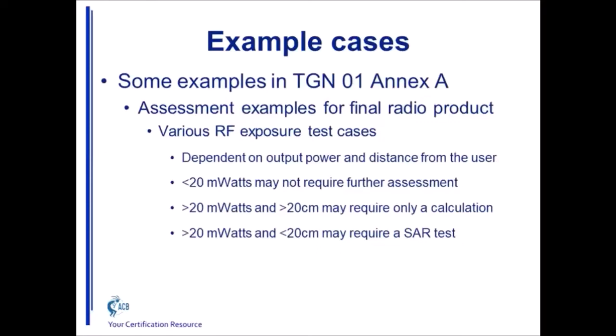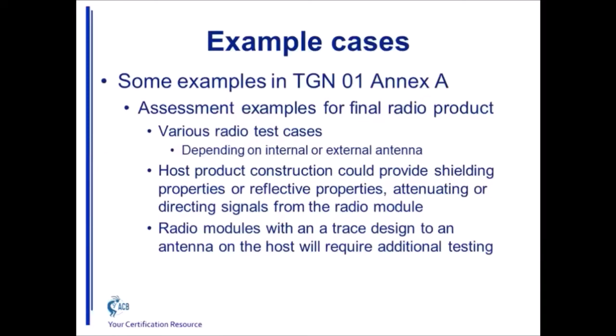However, if you're at a higher power and you're close to the body, this could be the head or your hands or your body itself, you may require a SAR test. So one of the assessment issues for a final radio product, again, depends on the various radio test cases. And this can be viewed as whether it has an internal or external antenna, because the host product construction could provide shielding of the module if there's an internal antenna, or it could affect spurious emissions and field strengths from spurious emissions, because you may have some shielding that could reflect and focus energy at some frequency. That's possible. And in the end, if you've got a radio module with a trace design to an antenna on the host, it will require additional testing because you changed the radio structure, the transmitting structure.